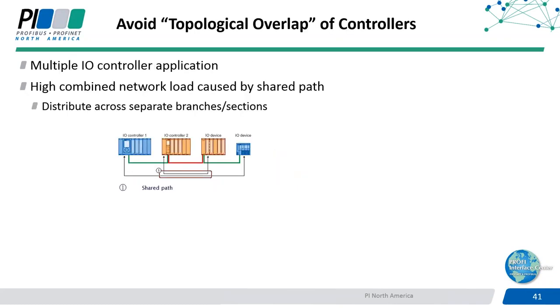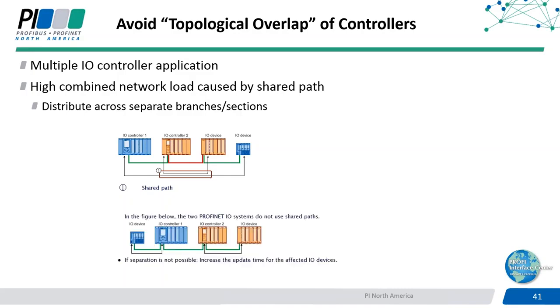Another tip on this network load is here. In case of multiple controller applications which are talking to their own devices, try to distribute the traffic evenly to avoid cross traffic. For example, you can see in this diagram we've got a line topology, with I/O controller 1 talking to its I/O device, and I/O controller 2 talking to its I/O device, and they've got cross traffic over that line. So it would be better for the communication layout to place the first I/O device closer to the controller, pretty much near, so we don't have that cross traffic through the switches.